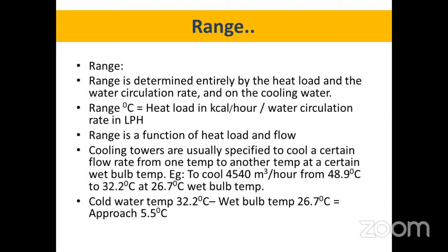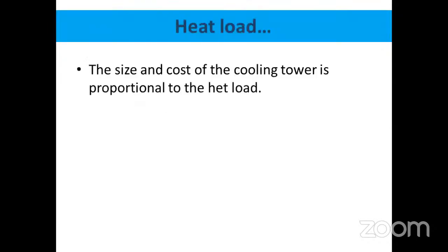We can see, 48.9 minus 32.2 is the range. Yes, it's the range, and 32.2 minus 26.7, the wet bulb temperature difference, is the approach. They are giving range and approach, and the capacity of water flow. In this case, 32.2 minus 26.7 is 5.5 degrees centigrade. That is the approach. The size and cost of a cooling tower is directly proportional to the heat load.